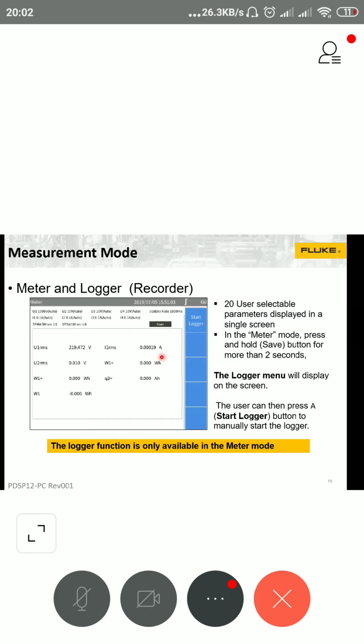So when it comes to an efficiency study of a VFD or a solar inverter, you can simultaneously measure all the three-phase voltage and three-phase current on the AC side, and on the DC side you can also measure voltage, current, power, all these things. With that, you can also check the efficiency in terms of percentage. Whatever you look at in the meter mode, you can put it for recording. The logger means it's a recorder, so you can put it for recording, and the data can be stored in the internal memory as well. If you are connected to a PC, you can store the data on the PC side also.